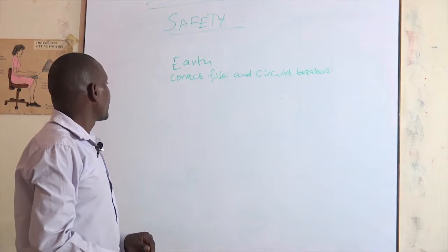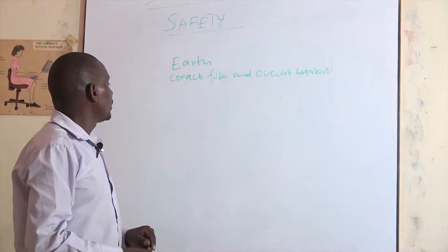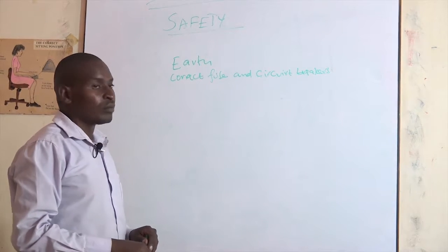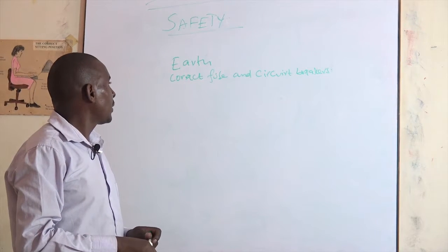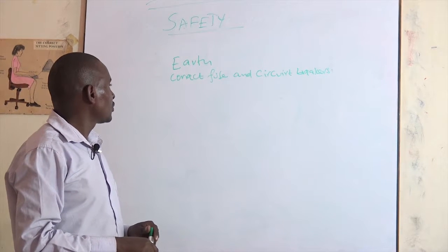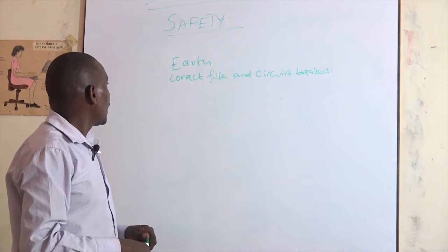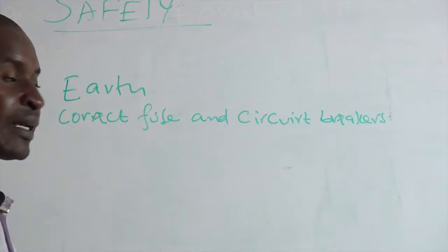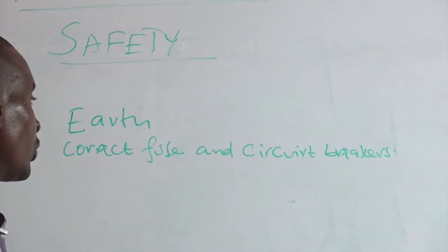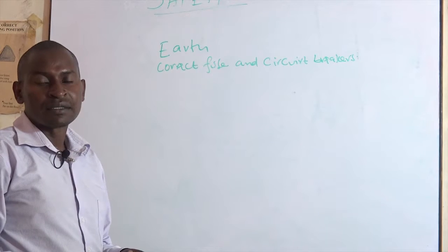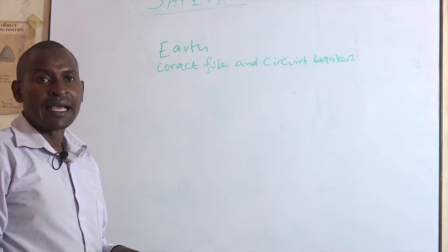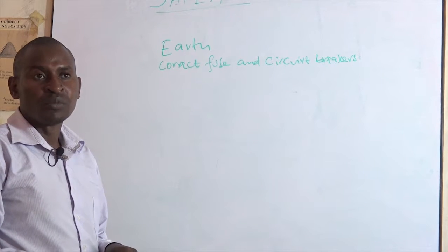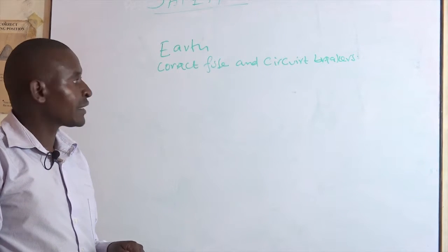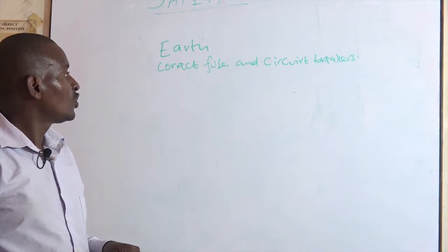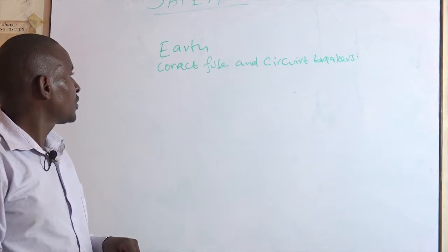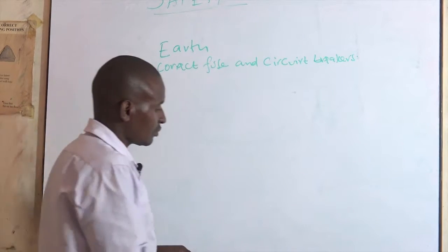We have seen that when we do earthing, we ensure that all electrical appliances, the metallic part and all the metallic part of the installation remain at zero potential. And if we use the correct fuses and circuit breakers, we ensure that we don't expose our metallic part that is generally earthed to any risk that there would be a rise in potential that would result in an electric shock.